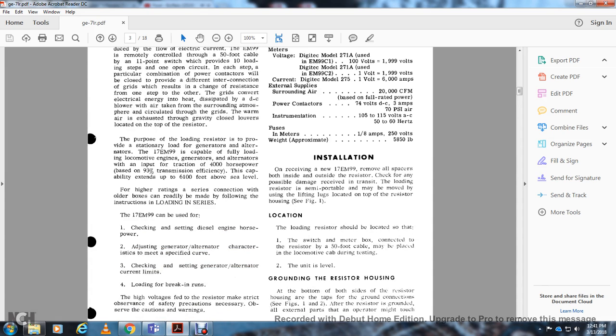Installation. On receipt of a new 17EM99, remove all the packing material both inside and outside of the resistor. Check for possible damage received in transit. The semi-portable loading resistor may be moved using lifting lugs located on the top of the resistor housing. Location: the loading resistor should be located so that the switch and meter box, connected with the resistor by a 50-foot cable, may be placed in the locomotive cab during testing.